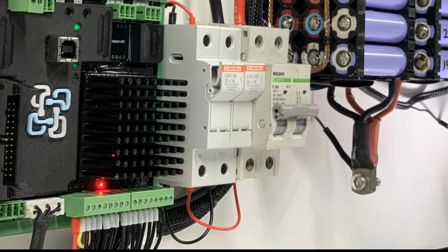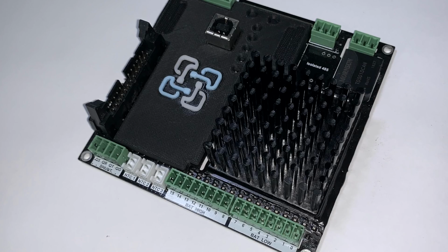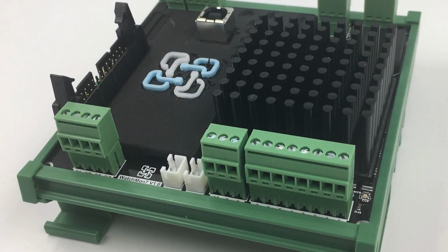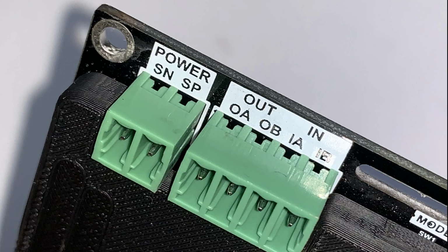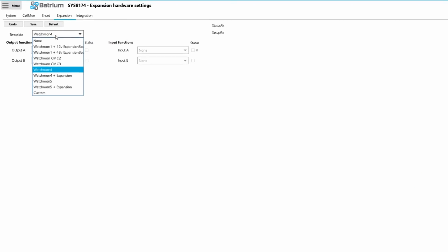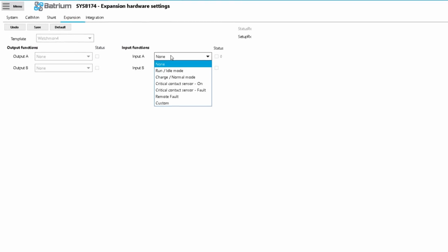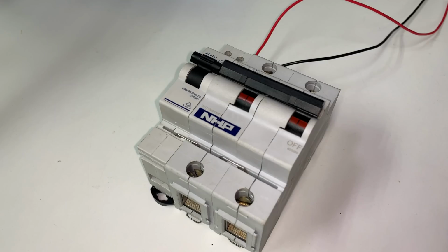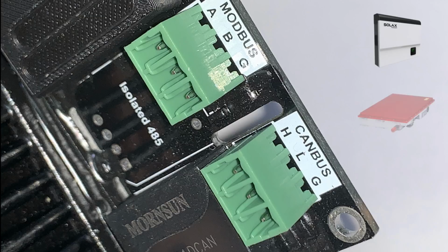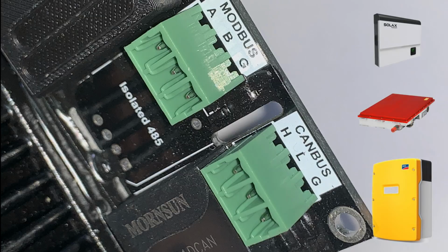There are two versions, a Watchmon Plus with 10 to 15S, and for smaller systems, a Watchmon 7 that will do 6 to 10S. They have two switch ground inputs, outputs. The functions can be user-defined with the Watchmon toolkit. Action examples would be controlling fans or triggering a shunt trip. To communicate with the remote systems, it has a fully isolated CAN bus port with an optional RS485 port.